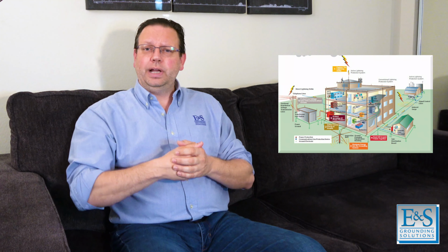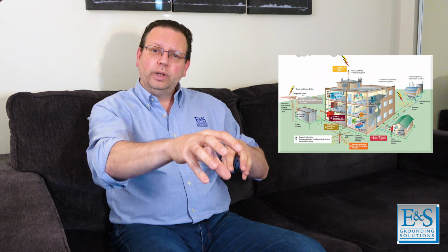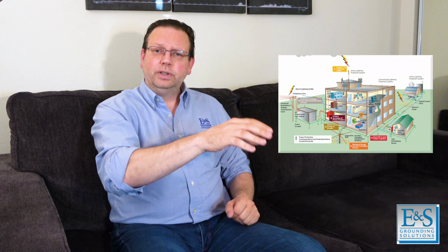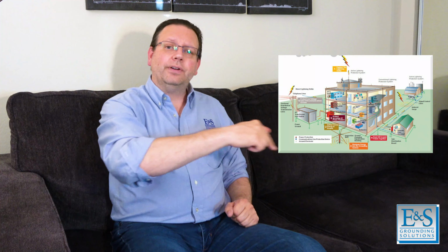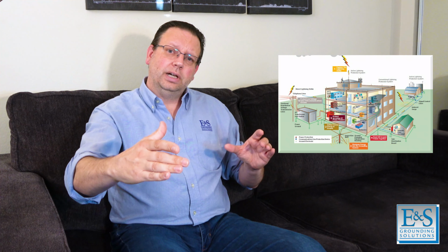Plus that ground, because we have so much current, right? That loop becomes our single biggest grounding electrode. If you recall, and you'd have to go back to our sphere of influence, when you have single ground rods, you're only talking about a sphere of influence. Say you have 4 10-foot ground rods across a 100 by 100 building. You have 4 10-foot spheres of influence on each of those ground rods. That's it. But if you have a loop, now you have the sphere of influence of 141 feet across that structure because you've got a 100-foot ground loop.